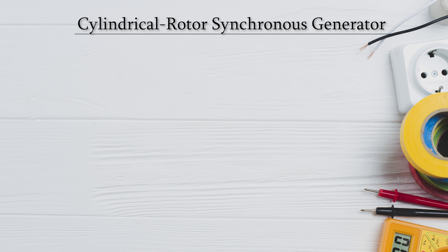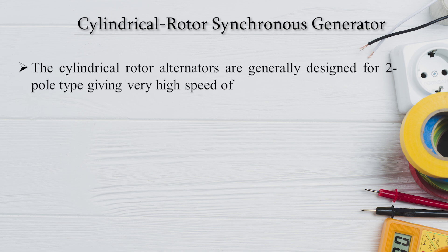Cylindrical rotor synchronous generators are normally designed as two-pole machines. Since synchronous speed NS = 120F/P, and normal power frequency is 50 Hz, with number of poles equal to 2, we get 120 × 50 / 2 = 3000 RPM — a very high speed requiring a cylindrical rotor synchronous generator.